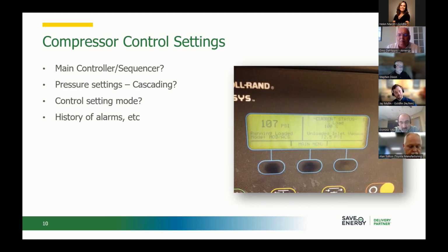Any of your favorites? Usually when they have multiple compressors, the incumbent service company will set them up in a pressure cascade, but depending whether or not there's the modulation mode or load unload mode, that's critical. I look at how they're set up. And I also look at the history of alarms. The history of alarms gives me a good idea what the compressors have been doing, how they've been operating, what issues have been going on with power or temperature or maintenance, and so on and so forth. So all that goes in an audit study.